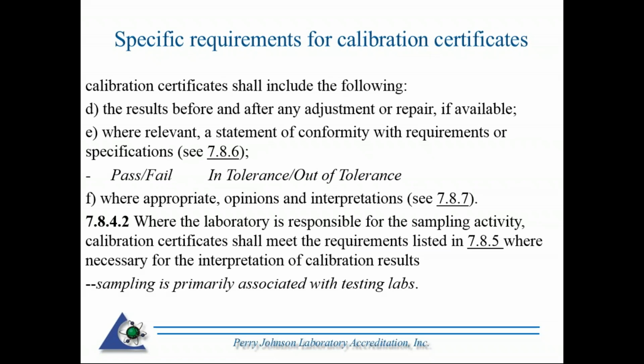Still on calibration results, the results before and after any adjustment or repair, if available. So if you are calibrating, let's say, a pipette, and it's out of tolerance, those instruments can be adjusted. So the before and after, as found, as left, would need to be captured if they're different. Sometimes the as found could be the same as the as left if there were no adjustments. Sometimes an instrument may not be operating at all when it comes in, therefore there was no true as found value data there.